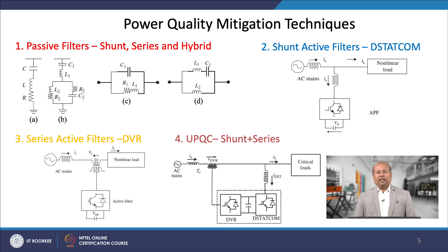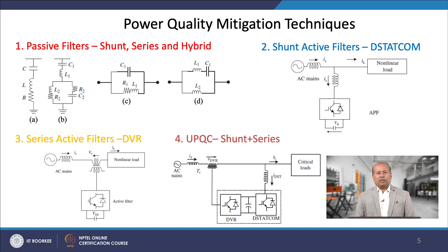Even though passive filters are extensively used in many applications, they have limitations. They are not adaptable to varying system conditions due to their size and tuned frequency, which cannot be altered easily. A change in system conditions will detune the filter and cause increased distortion. For an effective filter design, the overall impedance must be less than the source impedance. As a result, a large filter is required and causes over-compensation of reactive power. In consideration of these limitations, active power filters are an important and flexible alternative to compensate voltage and current related power quality problems in distribution systems.